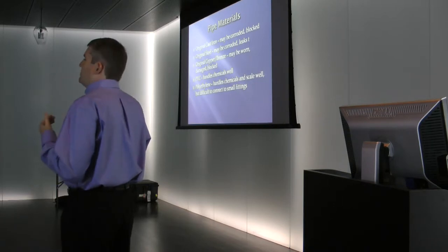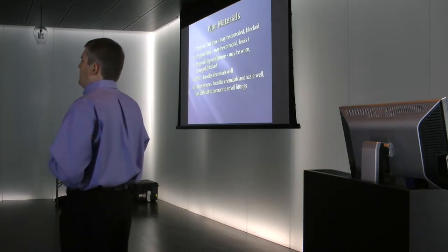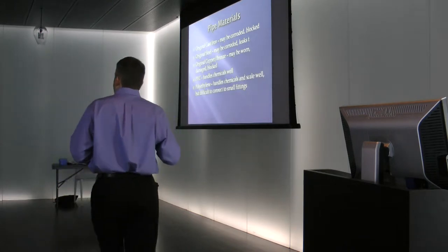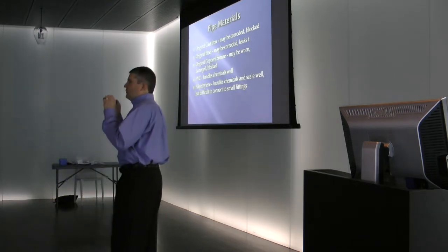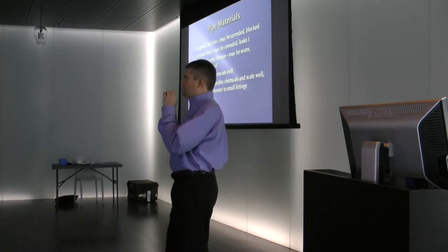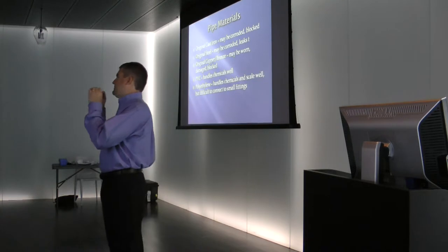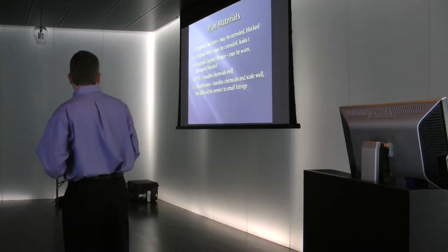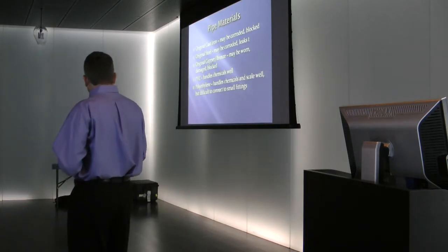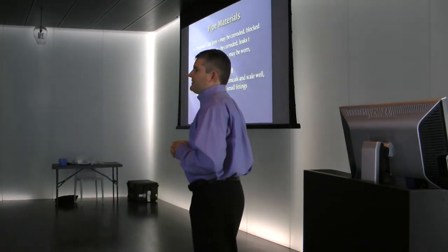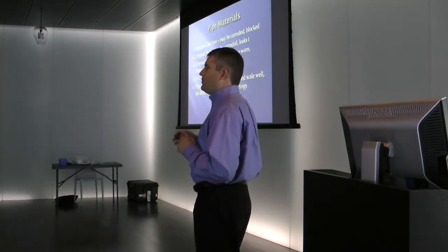But at higher temperatures, that rating actually comes down even lower. So sometimes with a copper pipe, you can't even run half of the flow rate that you can through an equivalent PVC pipe. Given PVC and copper, the copper sometimes only handles half of the flow rate of the PVC. So what happens with a lot of copper pipes is that the systems are just running too fast, and it'll wear holes through it.